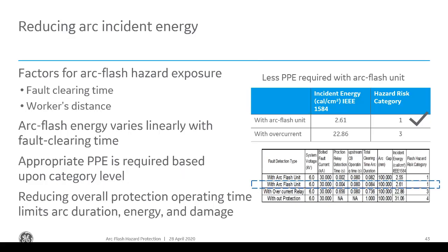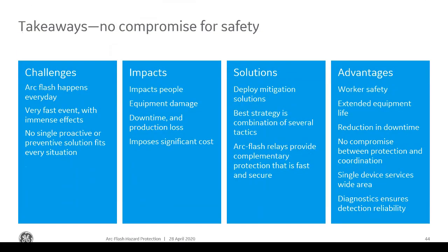Reducing arc flash energy: we're looking at using these arc flash units versus just the overcurrent, and you can see in this example a significant reduction from arc flash level 3 to 1. Most of the time you're going to be able to reduce it to an arc flash level of 1, assuming you have a fast acting or fast interrupting breaker. So we're reducing the PPE requirement or hazard for personnel safety, using either the light sensor or the bus differential.